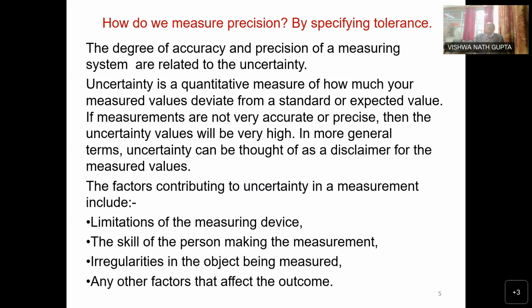Uncertainty plays a vital role in measuring how precise our output is; it can be quantified with the help of uncertainty. Earlier, when the concept of uncertainty was not there, there was only the standard value and the measured value, and the difference was the error. So by adding or subtracting the error we were reaching the standard value, but how much uncertain that was, we did not know.